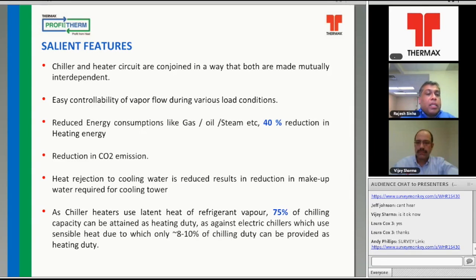Having said that, this has several advantages, like the easy controllability of vapor flow during various load conditions, and of course it's highly efficient. It reduces carbon dioxide emissions, and heat rejection is significantly reduced and can also be eliminated under certain circumstances. And this, of course, uses refrigerant water, so it is eventually a much better form of doing both refrigeration as well as heating simultaneously.